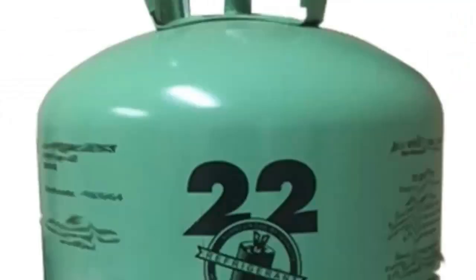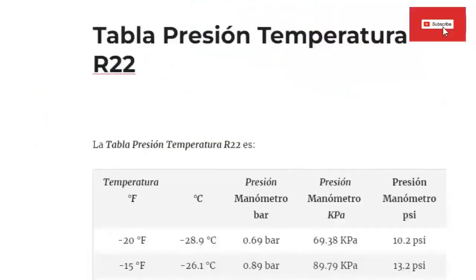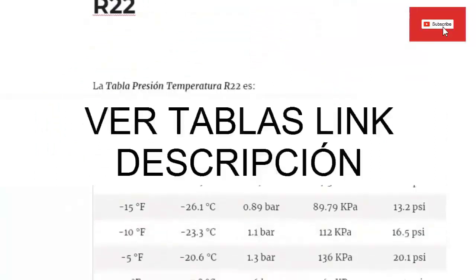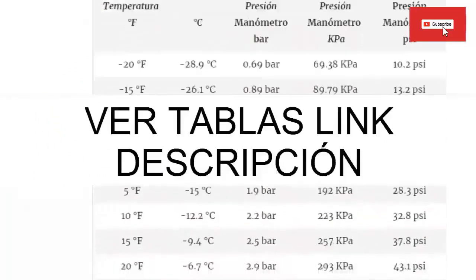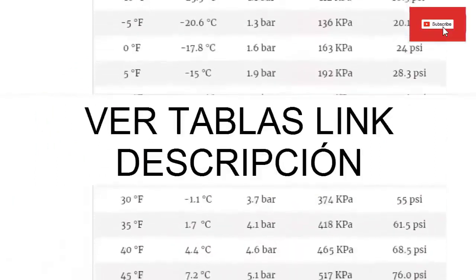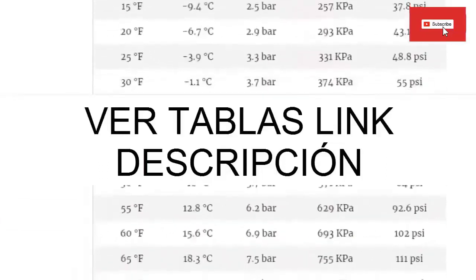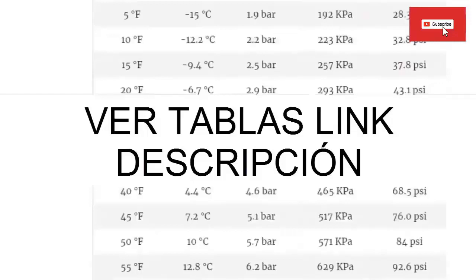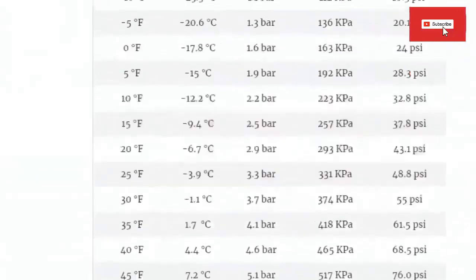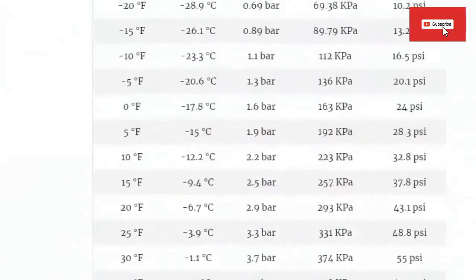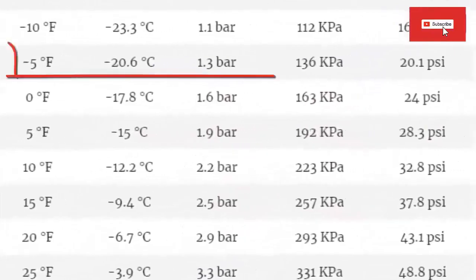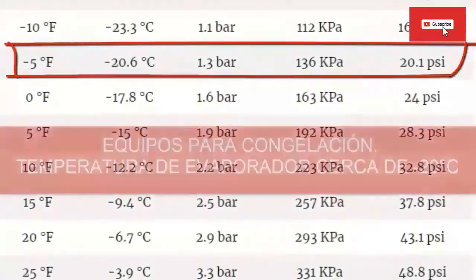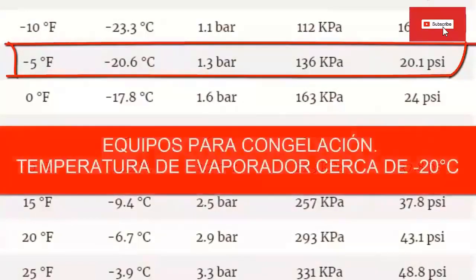R22 handles medium pressures. For a low temperature system — freezing to minus 20.5 degrees Celsius, approximately minus 5 degrees Fahrenheit — if we look in the table to reach this temperature in the evaporator, we need the equipment to mark a pressure on the low manometer of approximately 20.1 psi when turned on.